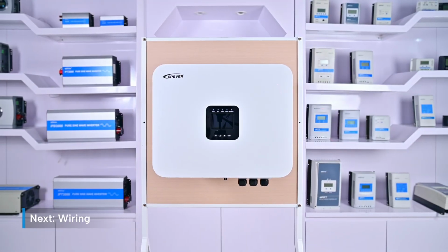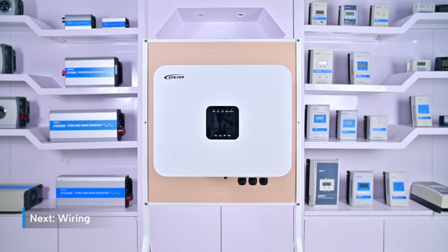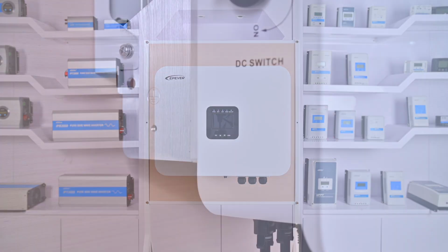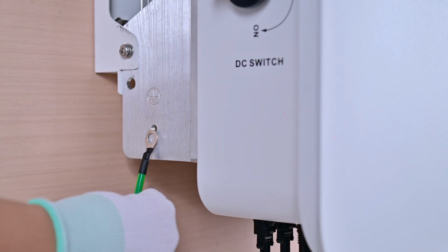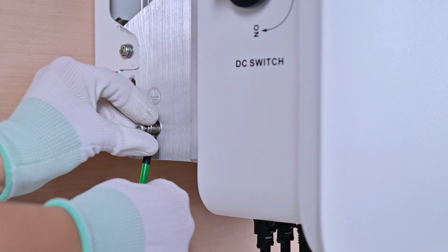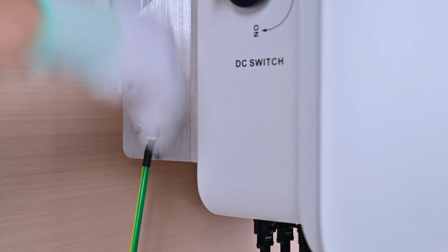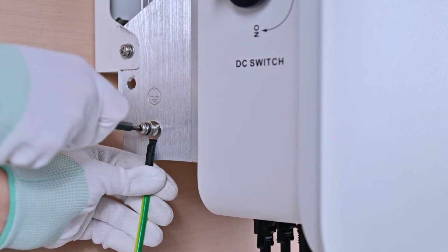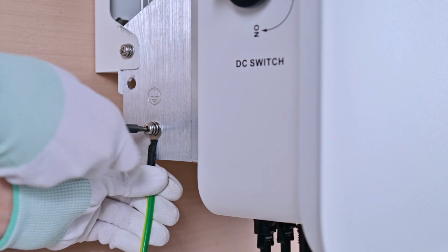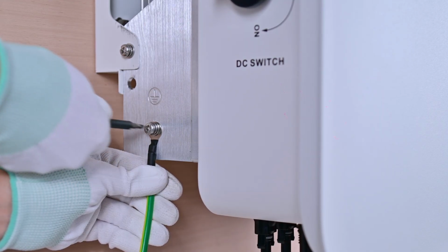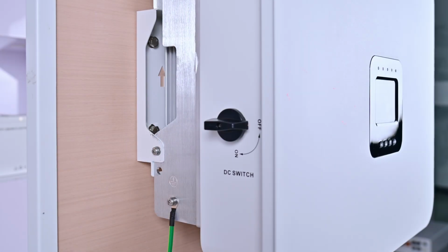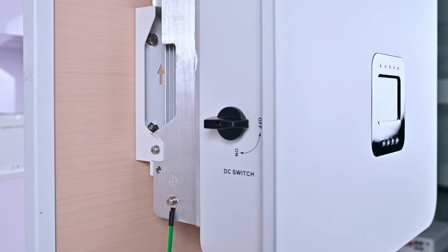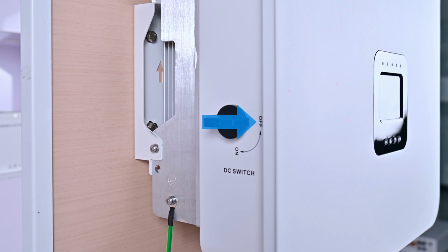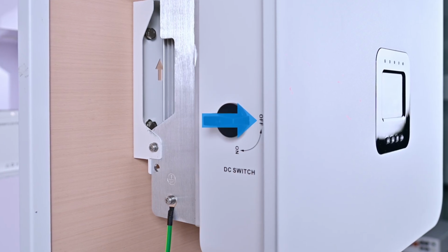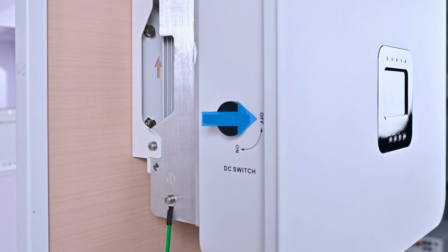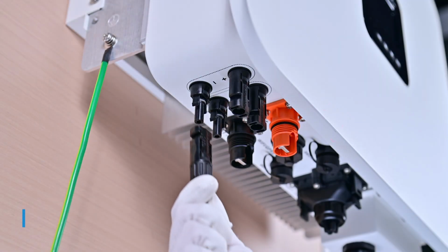Once confirmed that the installation is secure, we can begin the wiring process. First, ground the device. Next, connect the solar panel to the device. Before connecting, make sure the DC switch on the left side of the device is in the off position. Connect solar panel.